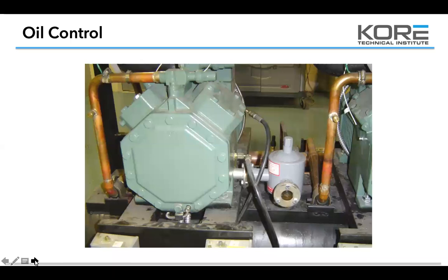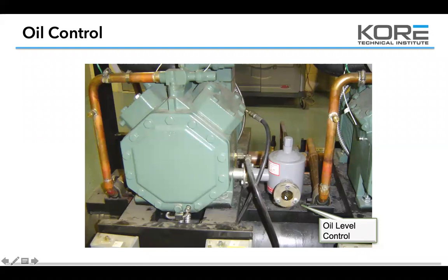For the oil separator oil level control — this is a mechanical float — the nut at the very top is where you make your adjustment, and it usually has a sticker on the side telling you exactly how to adjust it. We like to see about a half a sight glass of oil with Copeland's. You can get down to about a third, but no more than three-quarters. Start pushing past that and you're either starving or pumping oil. Ideally you want to see right in the middle of that sight glass. When checking your oil, look at level and also color — it should be a nice light brown. If it's POE or a synthetic it should be almost clear.